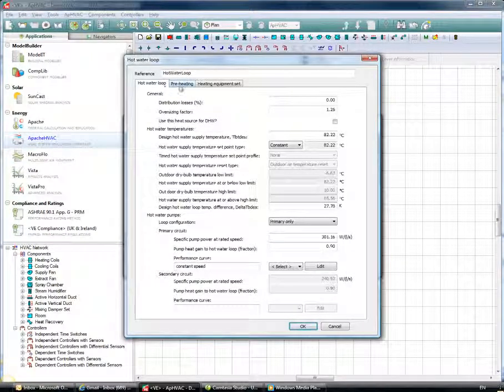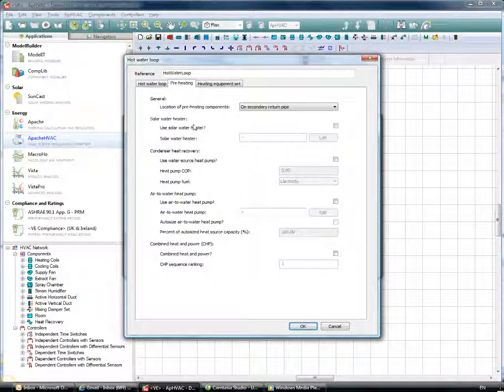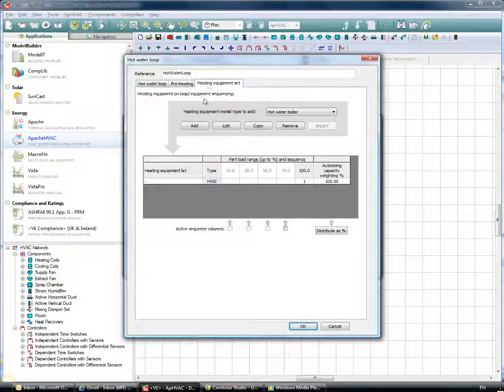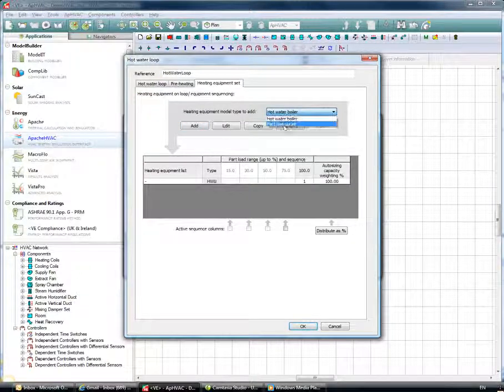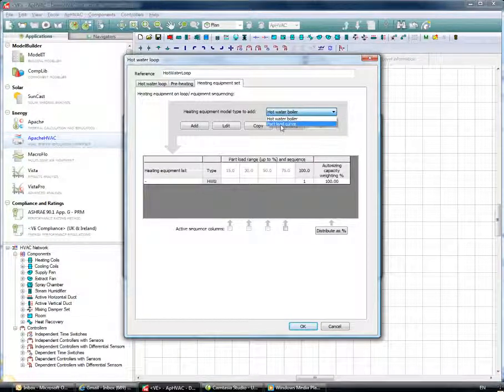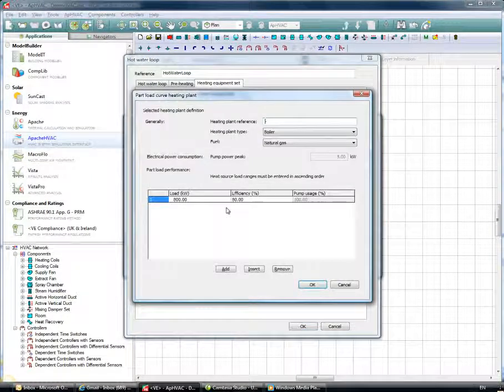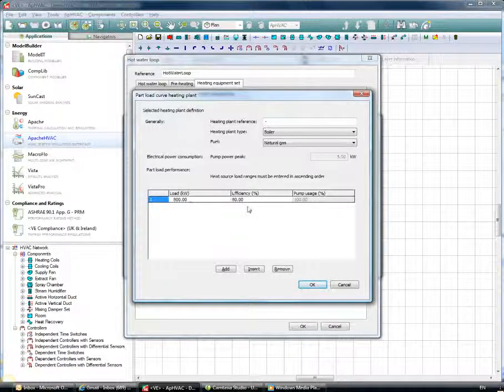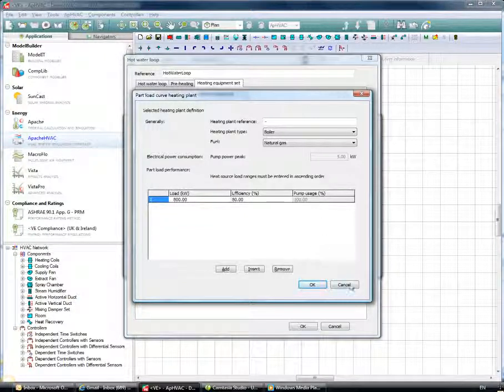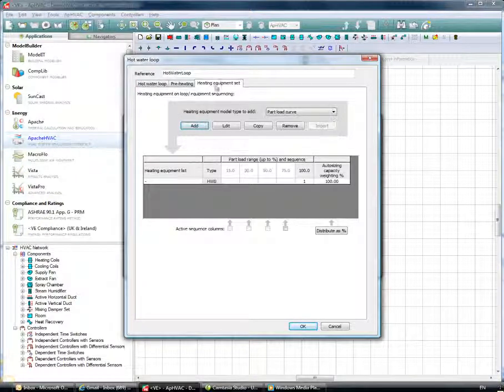Clicking the Add button for the hot water loop, I can see three tabs: the Hot Water Loop tab, a Preheating tab where we can model preheating devices, and a Heating Equipment Set. Within the Heating Equipment Set, I can choose from two types of heat generators: a hot water boiler or a part load curve. Those familiar with Apache HVAC from the past will know the part load curve, where you input load and efficiency. Pump information is now input within the other tabs of the hot water loop.